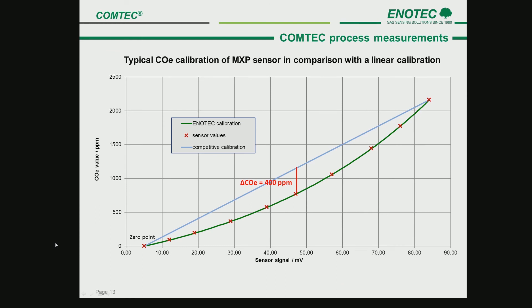Every Comtec sensor receives a comparative calibration. Several calibration points are determined to reach higher accuracy. The calibration points are determined by applying certified test gas to the sensor in different concentrations relating to the measuring range.